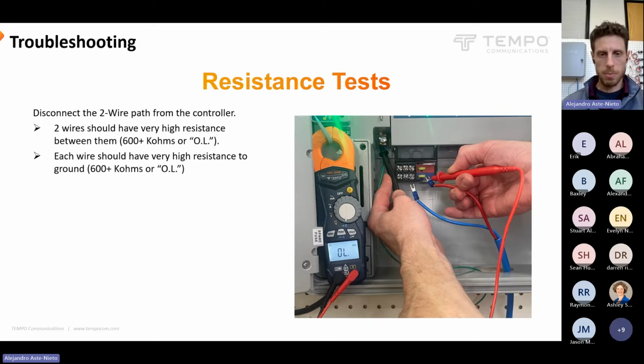And so we can test that, testing resistance between each of these wires and the ground lug in our controller, which is supposed to be grounded. So there'll be a ground wire. This is not a good ground wire. This is just on my test system here, but typically you see a very thick copper wire going to a ground rod or grounding plate, and that's supposed to be installed outside of a certain radius of the controller. But the point being, it's got continuity to the earth coming to this point in our controller.